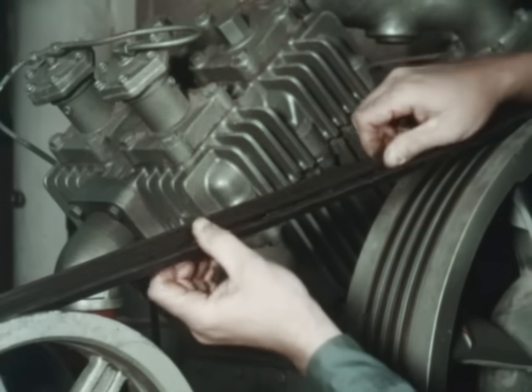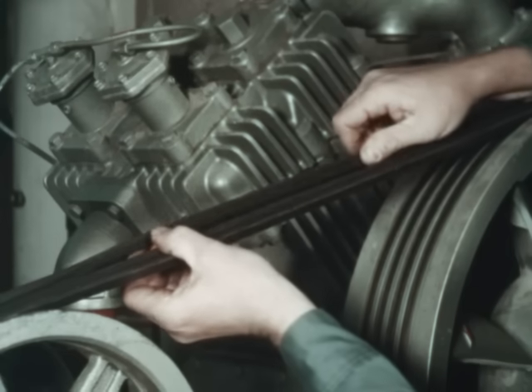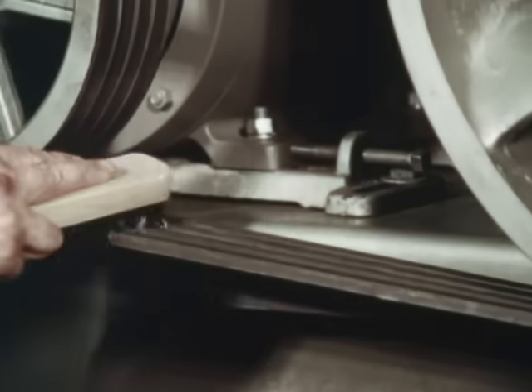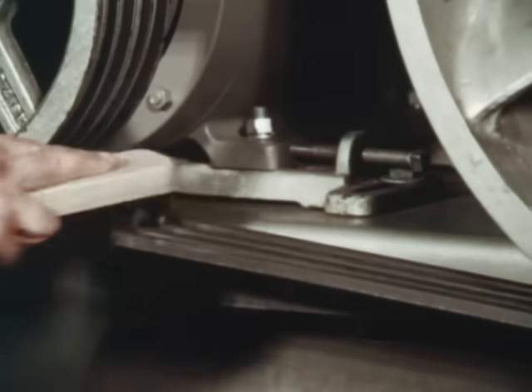Examine the V-belts. If they are cracked, frayed, or swollen, replace them with a matched set. V-belts should be kept clean. If dirt has been caked on, a stiff bristle brush may be used to clean the belts. Particles of dirt tend to embed themselves into the belts, making them coarse and rough, causing sheave wear.